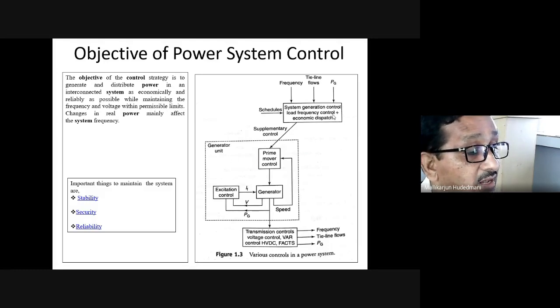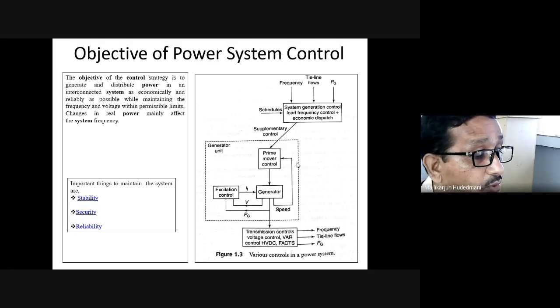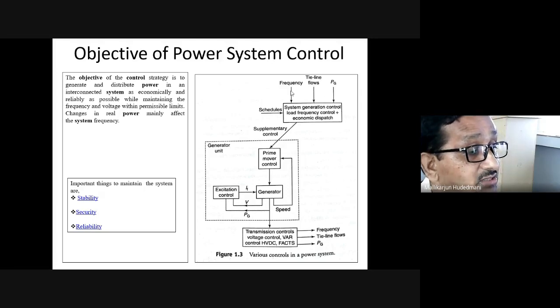What is the set point of this generator I am going to obtain, PG, and how long, with what generator, till what duration, that's called schedule. All these schedules, all these parameters combined together set up a stimulus to the generator system mechanism, which controls the prime mover, which controls the input to the particular turbine, which will drive the generator. When this generator is being driven, it definitely generates electricity. Once it generates electricity, it has to have RPM feedback to control, which is nothing but frequency control. We have a specific frequency requirement, but to attain that certain frequency, the RPM of the turbine has to be managed. Then speed is fed back.